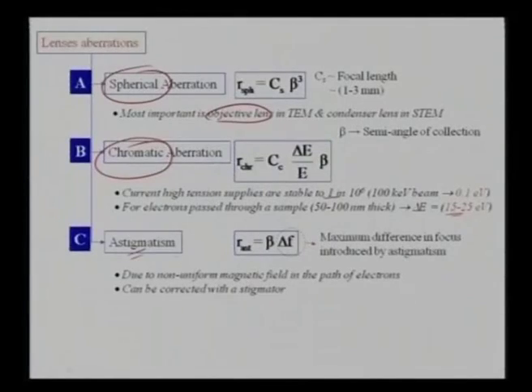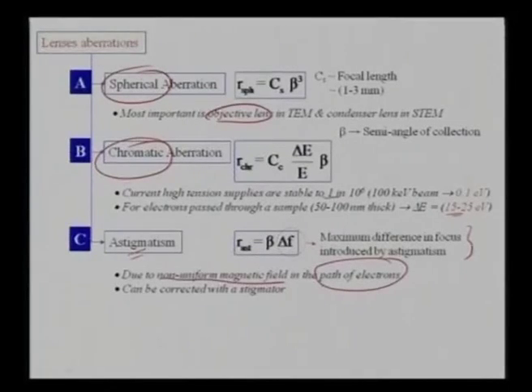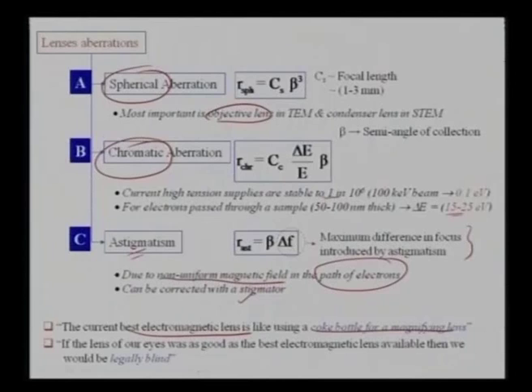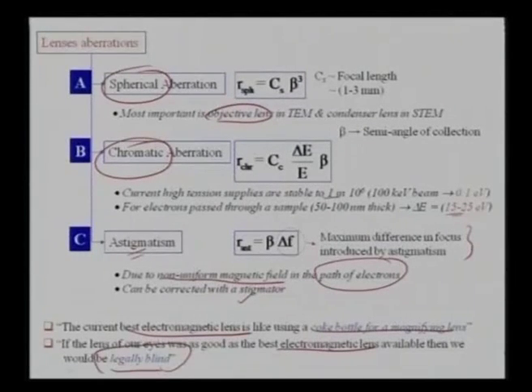Astigmatism means that beams traveling horizontally and vertically do not focus at a single point. This is because lenses may be stronger at certain points, causing them to focus at different lengths. Astigmatism means the vertical and horizontal scales do not match up properly due to non-uniform magnetic fields in the electron path, and can be corrected using a stigmator. With all these aberrations, even the best electromagnetic lenses are like using a coke bottle as a magnifying lens — so much aberration exists that if we scale it to our eyes we would be legally blind.